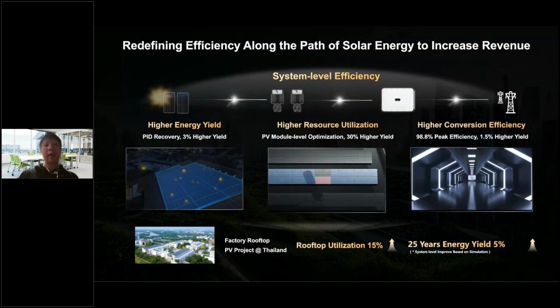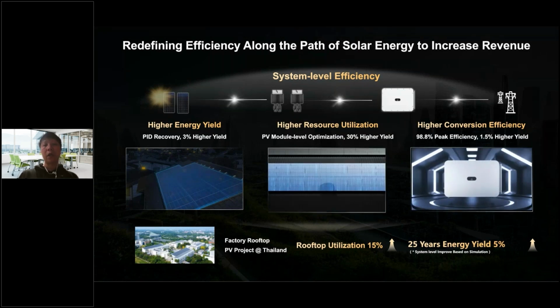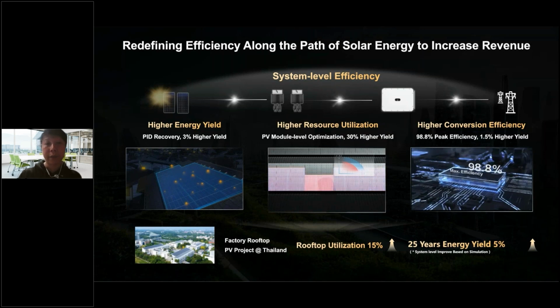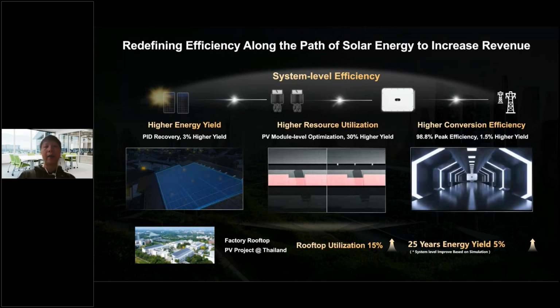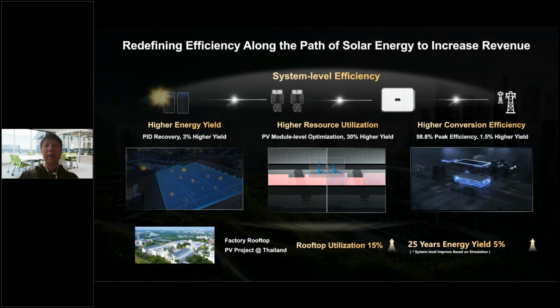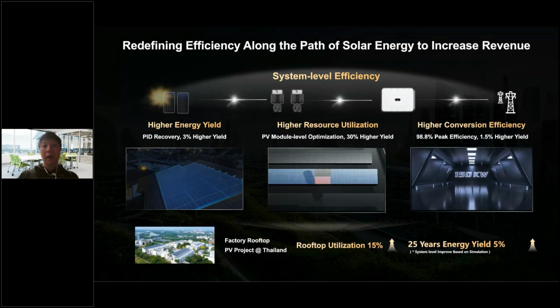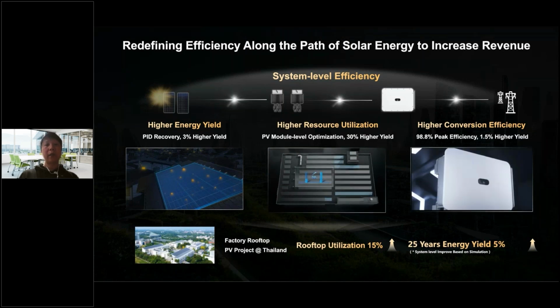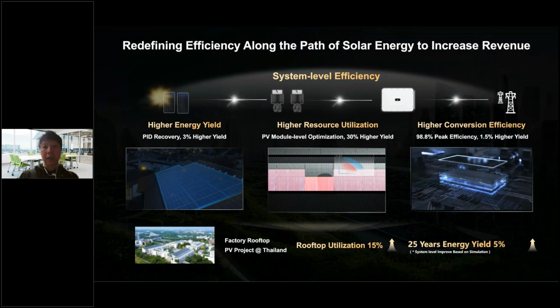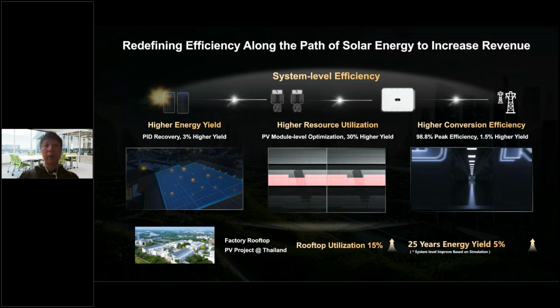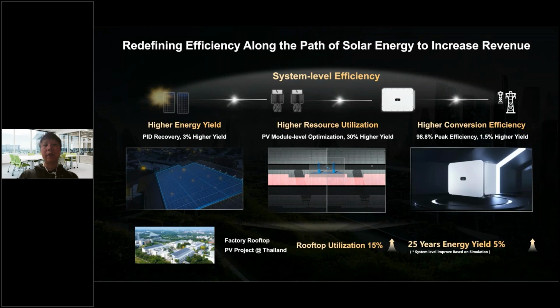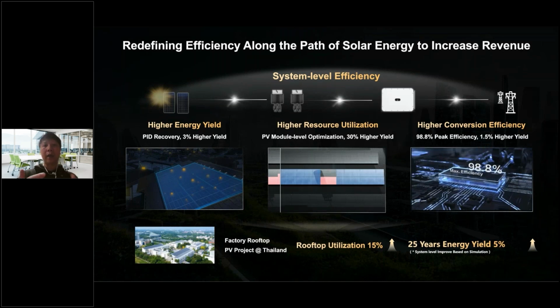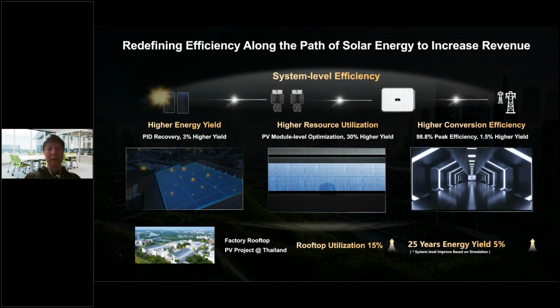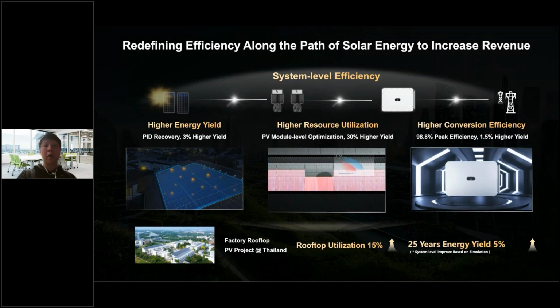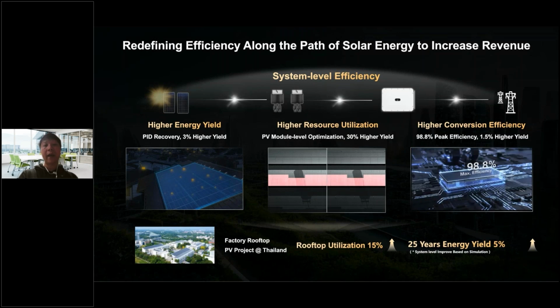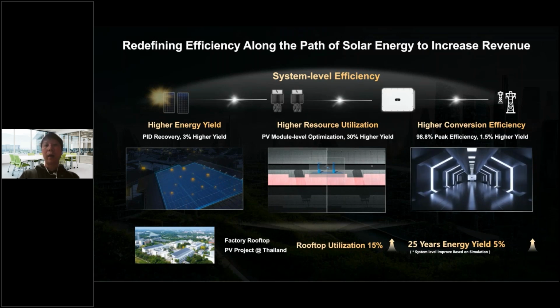And on the modules, we have this kind of a PID recovery feature. This PID recovery feature is built into the inverters. So in some high temperature and high humidity environments, there might be degradation problems during the daytime. But for Huawei inverters, we have this integrated PID recovery feature. Which means we will inject the voltage during the night, and we'll recover the PV modules during the night. So if the modules were affected during the daytime, this will be recovered during the nighttime. And TUV gave us the report that with this PID recovery feature, the inverters can have like 3% higher energy yields during the lifetime. So that's the PID recovery feature.